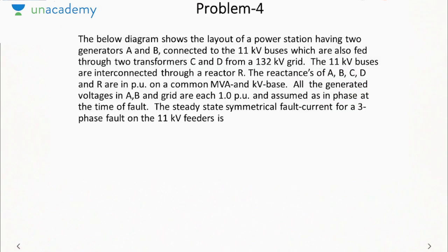Now the reactances of A, B, C, D and R are in pu, on a common MVA kV base. All the generated voltages in A, B and grid are 1 pu and assumed as in phase at the time of fault. So VA is equal to VB is equal to V grid. It is saying they are 1 pu and all are in the same phase. Since all are in the same phase, it implies that all the angles will be same. I am assuming the angle as 0 degree. The steady state symmetrical three-phase fault current on the feeder.